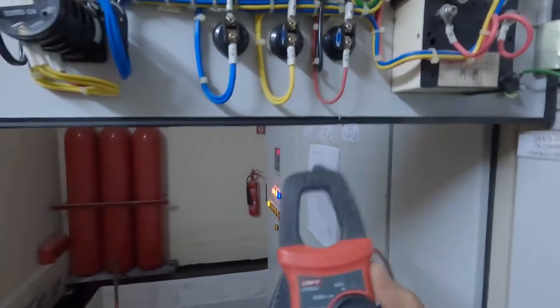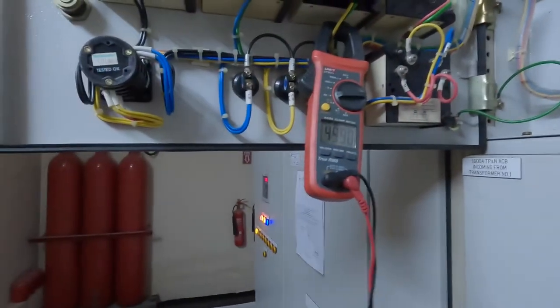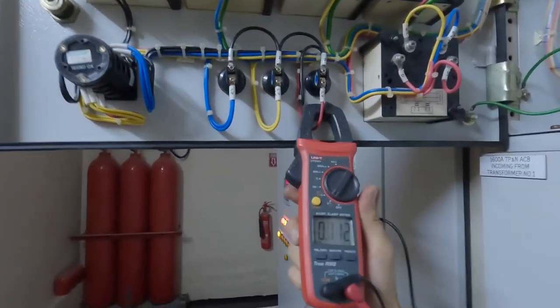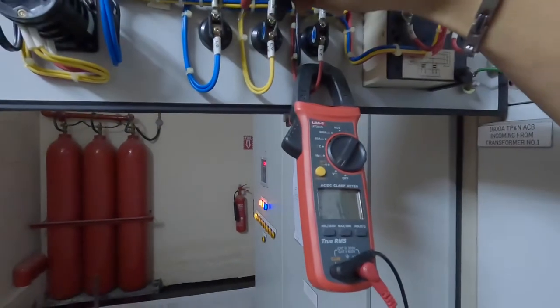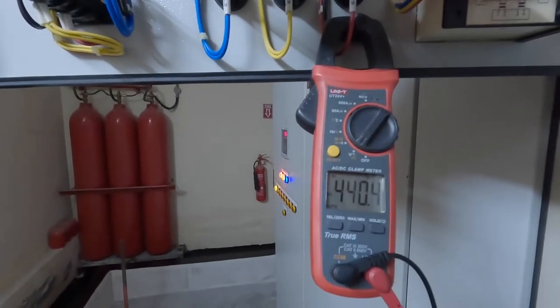On the frequency side — 50 Hz, no issue. On three phase, if you're using a 440V capacitor bank, it can easily get faulty because of the higher voltage range. Let's measure the three-phase voltage — it's about 438V. Yellow and blue phase is the highest at about 440V and a little more. This is higher than the permissible range of the transformer voltage rating.